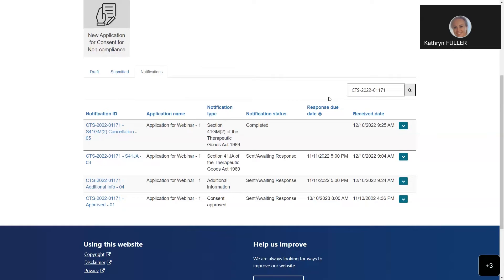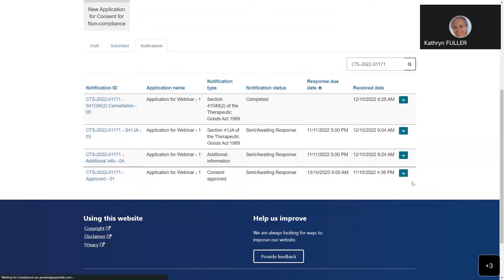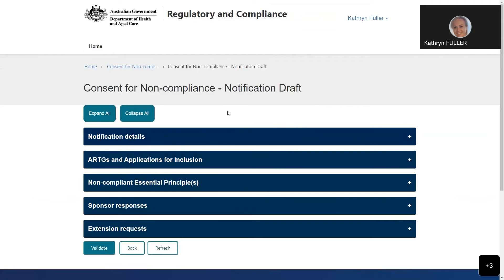When a consent application is approved, a notification and letter of approval is issued by the TGA and will appear in the notifications table. As part of the consent process, sponsors are required to provide evidence of compliance with the essential principles before the end of the consent period, and you provide this evidence as part of your response to the consent approved notification. You can submit your evidence of compliance in multiple responses as devices within the consent application become compliant throughout the consent period - this is different to all other notifications where you can only submit a response once. So the consent approved notification is a little bit special.